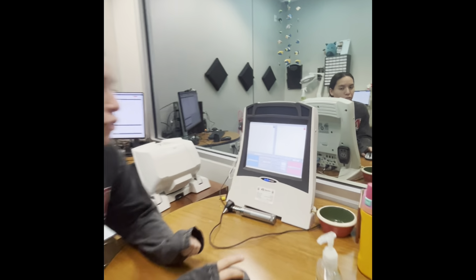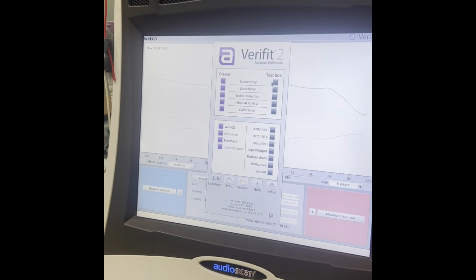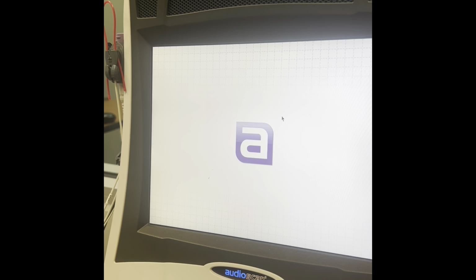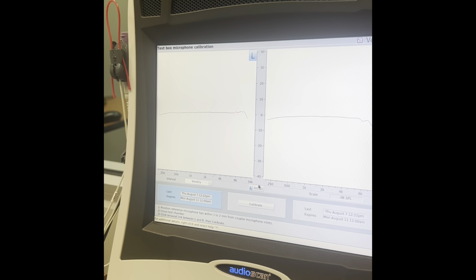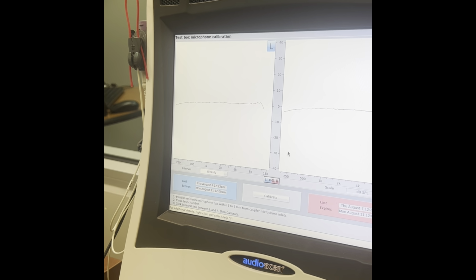Today I'm going to be doing real ear measures and speech mapping. So first we need to come over to ANSI and we're going to calibrate our test box. So we'll go to calibration. We're going to pair the two sides and I'm going to make sure there's nothing on our coupler mic. And then we're going to line up our reference mics on the side of our coupler mic, like this. We're going to close it. And then we're going to calibrate.